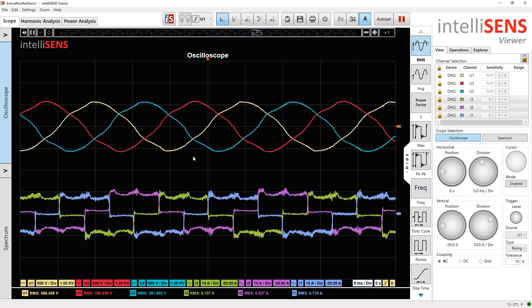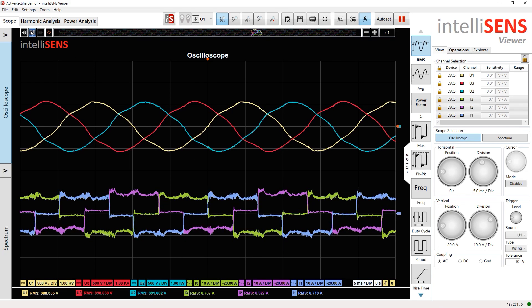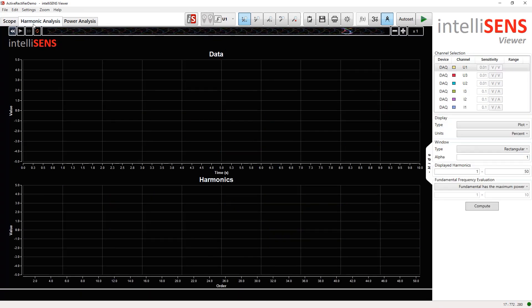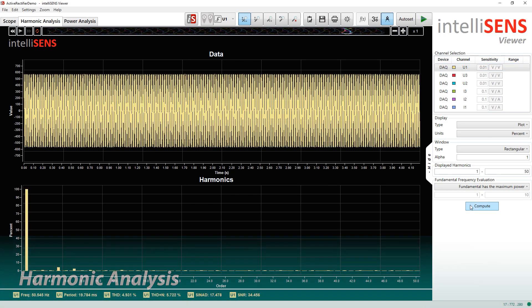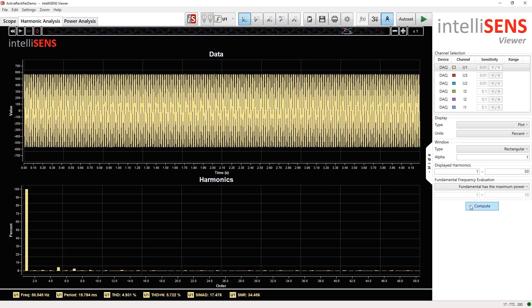Let's analyze the distortion in grid voltage, as they will ultimately affect the current waveforms as well. For that, we move to the harmonic analysis tab, select a voltage channel, and compute the results. We have around 5% THD on the grid side.